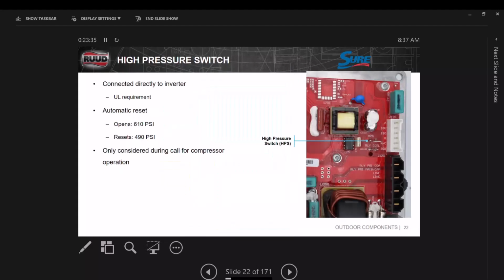Here's your high pressure switch on the board, and there's that relay coil we talked about a little closer up. Now the high pressure switch is an automatic reset switch. It opens at 610 pounds and resets again at 490 psi. It's only considered during a call for the compressor, so it won't open unless it's got a call to the compressor operating.